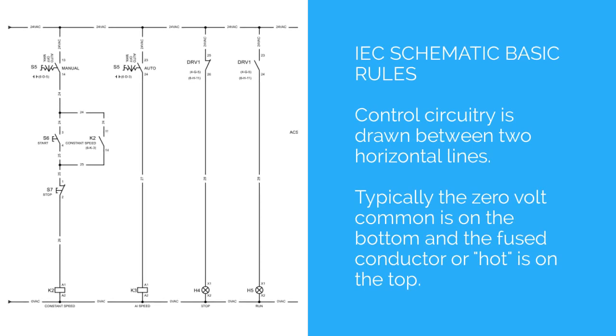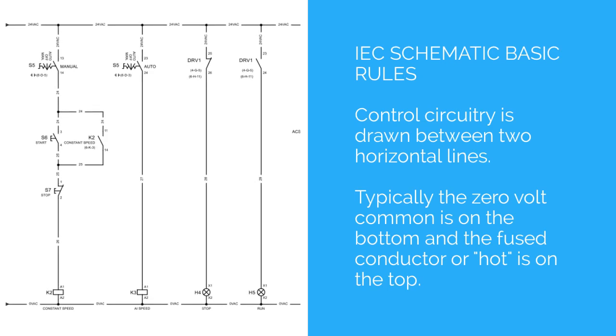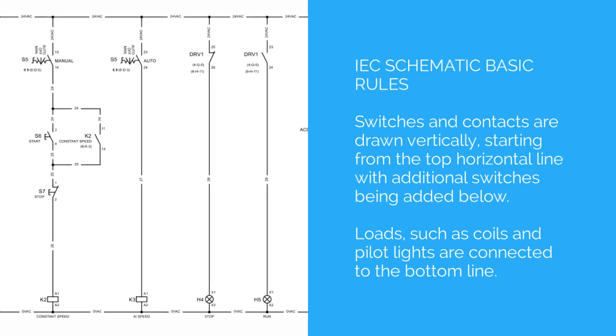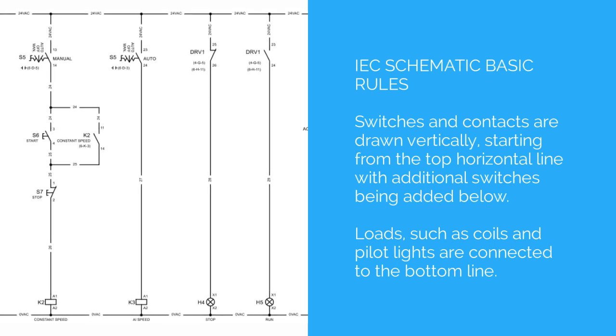IEC schematic basic rules: control circuitry is drawn between two horizontal lines. The fused conductor or hot is on the top, and typically the 0V common is on the bottom. Switches and contacts are drawn vertically, starting from the top horizontal line with additional switches being added below. Loads such as coils and pilot lights are connected to the bottom line.